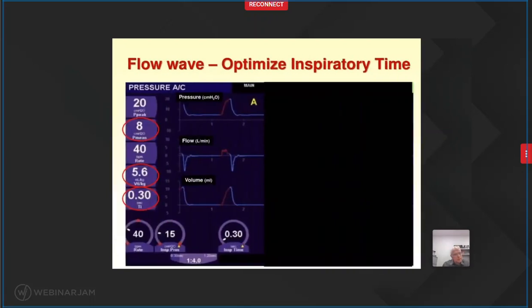So this one again is supposed to have an animation showing the difference when you increase the inspiratory time. I'll try to explain and see if you can understand. So here we have a baby that is using an inspiratory time of 0.3 seconds. The volume is 5.6 mLs per kilo, and the mean airway pressure is 8. So if you were to double that inspiratory time, let's say from 0.3 to 0.6 seconds, what's going to happen is your mean airway pressure definitely is going to go up. It's going to go up to 11 or almost 12.